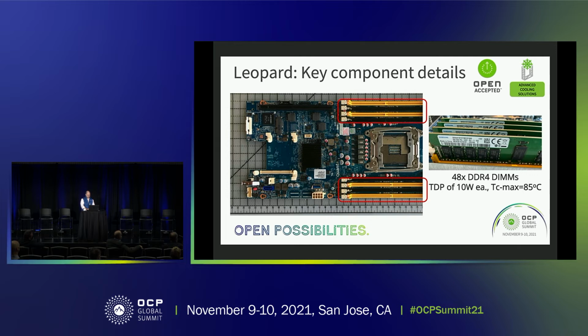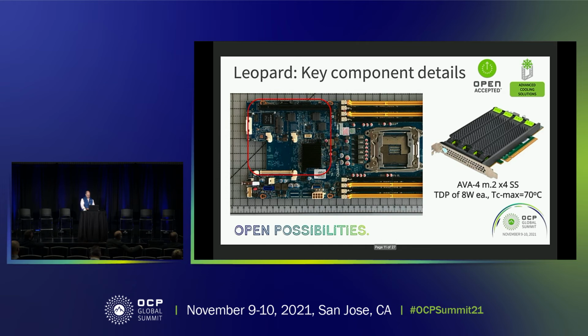So we do pay attention not only to the CPUs, but the other components adjacent to that. The density of the DIMMs is quite low compared to the heat sinks, so that's really a risk factor we need to consider. As we said earlier, on the next slide you can see the densest region, which is downstream now on the left of the CPUs - these AVA boards.